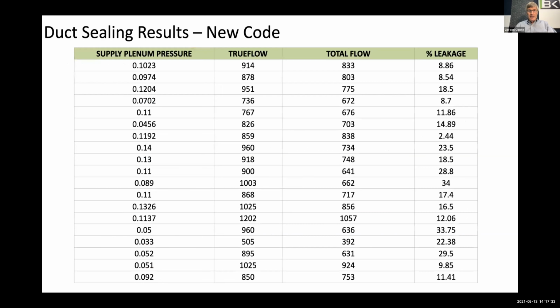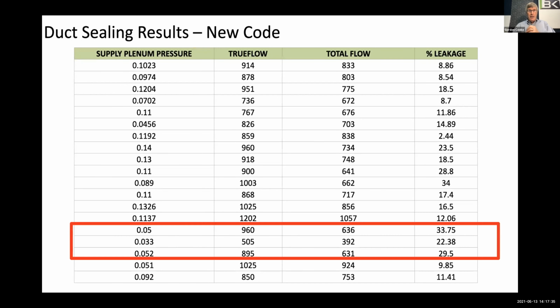So the duct sealing is kind of nice. This was a survey we did after the new code. Look on the right-hand side. The second last column is the total flow. We measured the flow at the furnace, we measured the flow out of individual grills, and we watched the difference. The difference was 18 to 20%, or I'll say 20 to 25, some as bad as 30%. So when I say duct leakage, you'll see some really good ones there, 2.4%, so that's great.